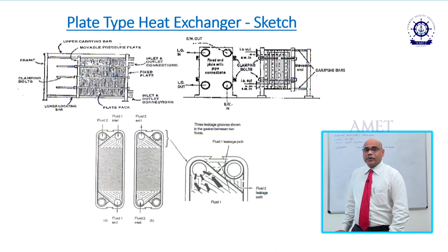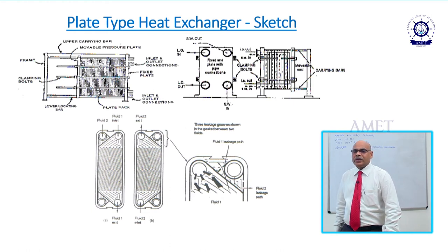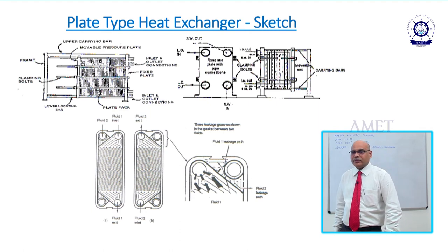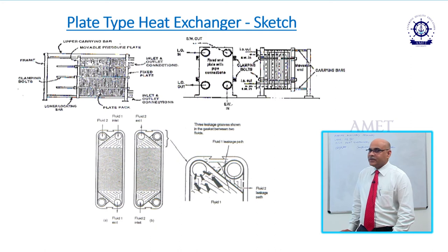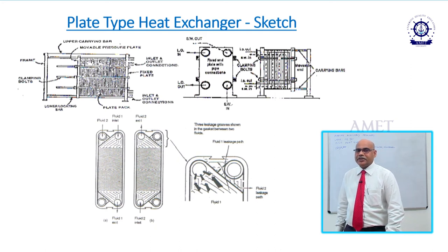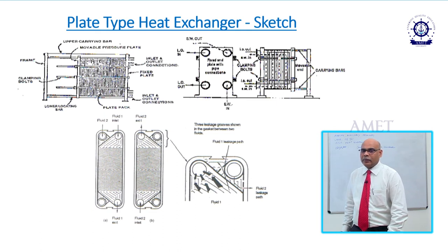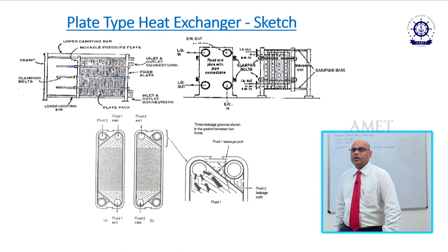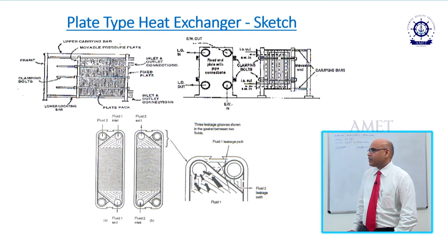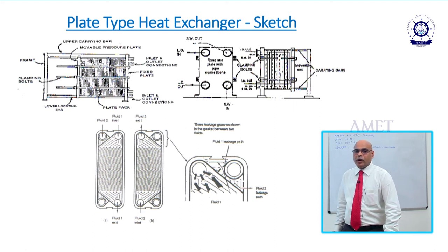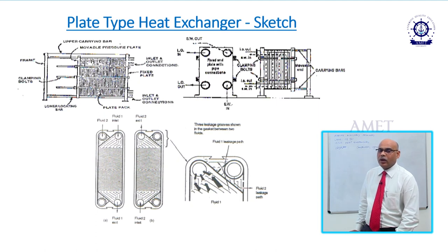While assembling, ensure the gaskets are properly stuck to the plates; if required, use a special glue to paste them back. When tightening, the plates must be tightened in a specific pattern as specified in the manual. This prevents over-tightening in a particular area — either top or bottom — which would cause changes in the shape of the plates. Follow the specific pattern as specified in the manual.